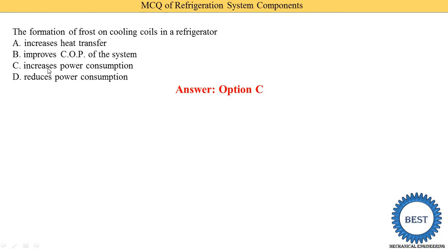Due to this frost formation, the heat transfer is reduced. And when the heat transfer is reduced, the temperature of the refrigerant is not increased at the outlet of the evaporator, and this increases the power consumption of the compressor.